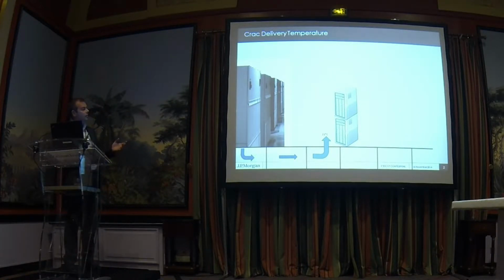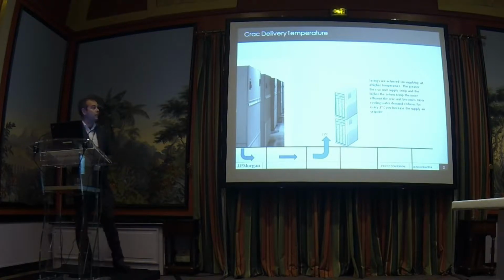So it's a very fine balance between how much air, too much air, too low a temperature, or too high a temperature. The savings are achieved with higher temperature supply. The greater the CRAC unit supply temperature, the higher the return temperature, the more efficient the CRAC unit becomes. So for every degree you go up in set point on the supply air, your cooling valve will then shut down, give or take whatever the load is in the machine.